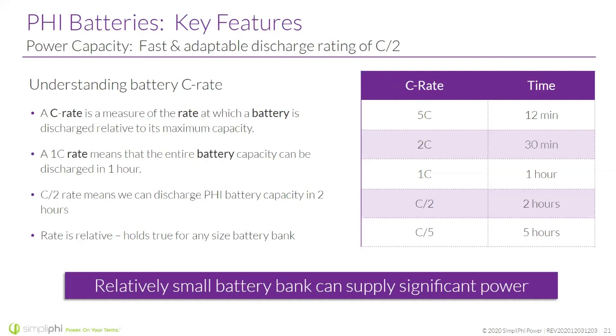Most people are not really interested in discharging their batteries in 1 or 2 hours. They typically size their batteries with enough capacity to run their home for 12 to 15 hours. But everybody wants to charge their batteries really quickly. They want to start up their generator, or use the grid, or a very large solar array, to charge their batteries in 30 minutes to an hour. You want to minimize generator runtime because you're paying for the fuel. Typically, batteries that can charge at a rate of 1C, 2C, or 5C have an active cooling system. They're less efficient, but they're important for things like cars, where you're parked at a supercharger running at high power, so your round trip efficiency is lower. But that's how you can charge at such a quick rate.